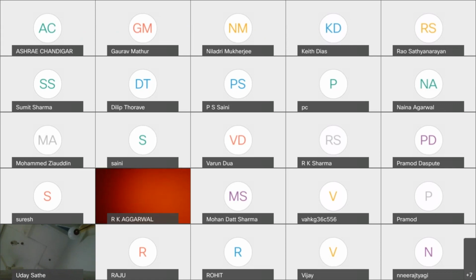Now, the next question: is it necessary to have an individual pump for each AHU in the plant room, or can it be proposed for a group of AHUs in the plant room? A very good question. If you go for a group of AHUs for a plant room, then it essentially becomes a pressure-based control. Here the AHUs which you are clubbing, as you have seen in the way we club the FCUs, you have to get the temperature signal of the return air or the supply air, and there has to be some device which modulates based on the temperature control for that particular AHU. So if you have a set of AHUs connected, then it becomes a zone-based system where the control is on differential pressure instead of temperature. It will not essentially be distributed pumping, it will be zone pumping.